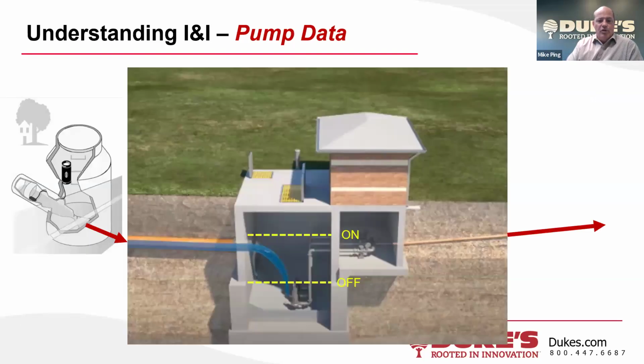So when you look at a pump station, I've got my flow meter over there on the left. It's possible to measure the flow directly with the open channel area velocity meter, just on the influent side of the pump station. Now sometimes that's undesirable. The wet well level, you can see my on-off where the floats would be. Quite often the wet wells are allowed to fill up to the point where the pipe is essentially backing up every single pump cycle.